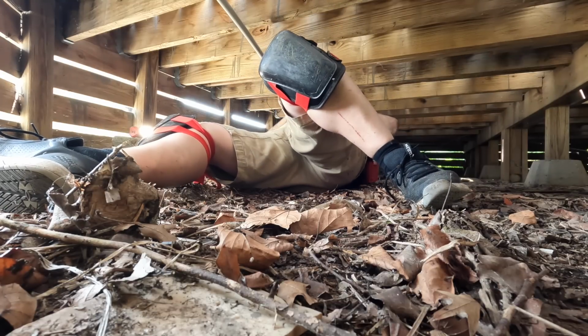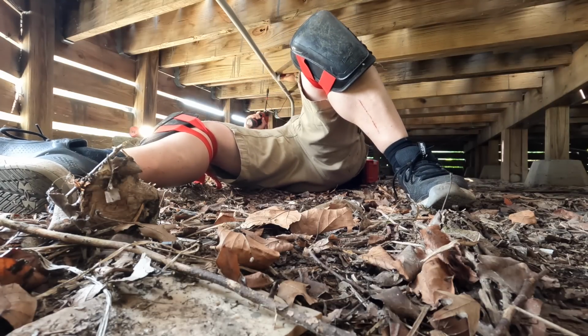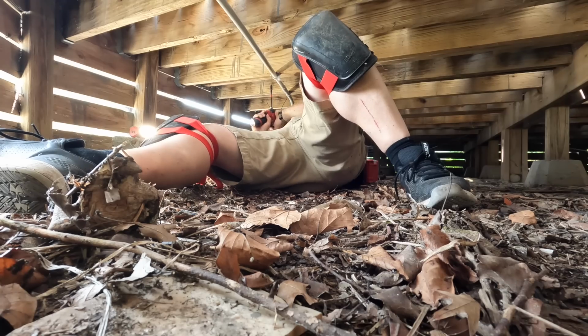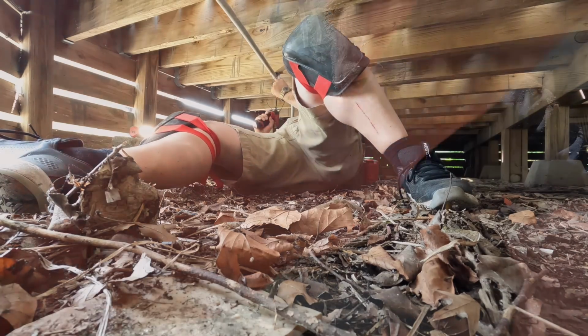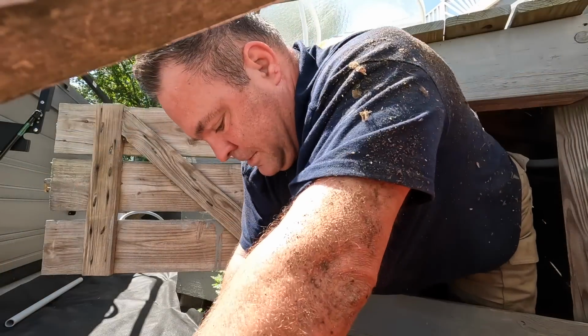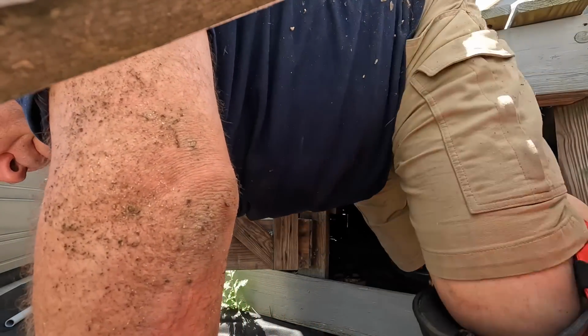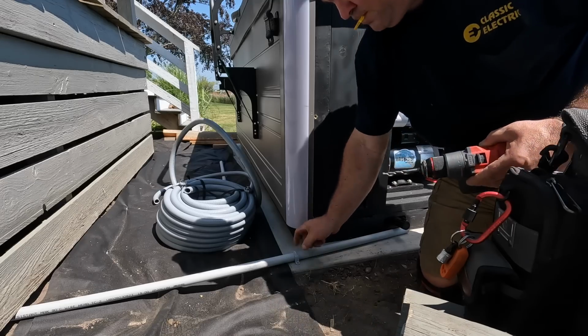For 3/4 inch PVC, you're supposed to have a strap every 3 feet. That's in the code section for the PVC, in case you were wondering. Yeah, so as you can see, I got awfully dirty down there, but that's okay. I'm all right with that.